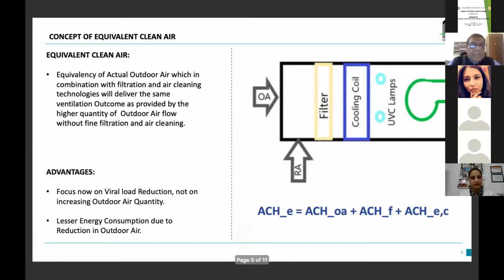So to minimize the impact of higher outdoor air requirement, the concept of the equivalent clean air approach has been getting prominence. You can see from the sketch on the right that this is an AHU where the outdoor air is coming and recirculated return air is coming. In normal cases, the minimum required outdoor air is provided. When the viral load has increased, you require more outdoor air, and more outdoor air consumes more energy.